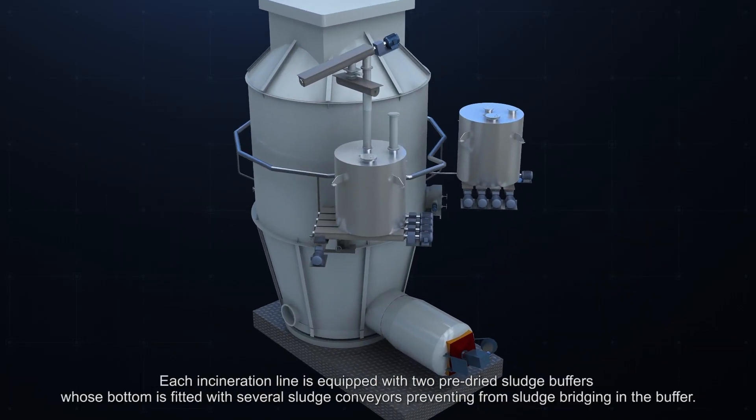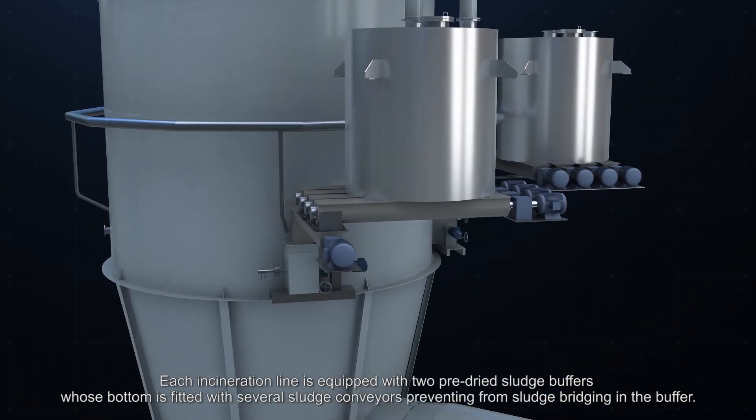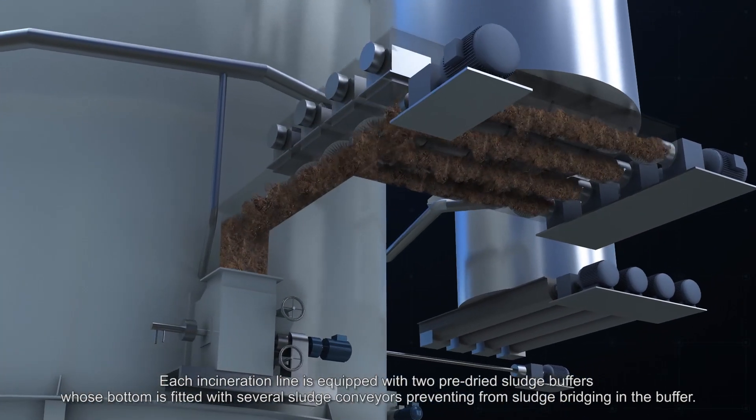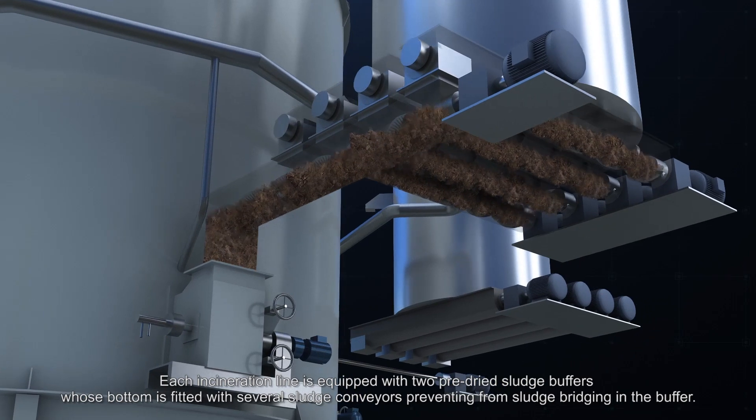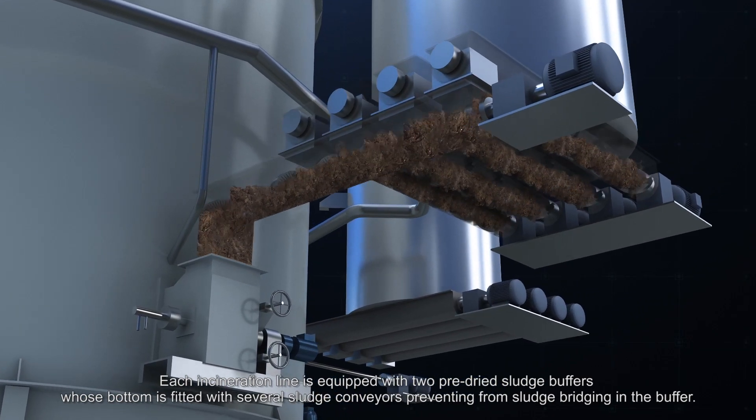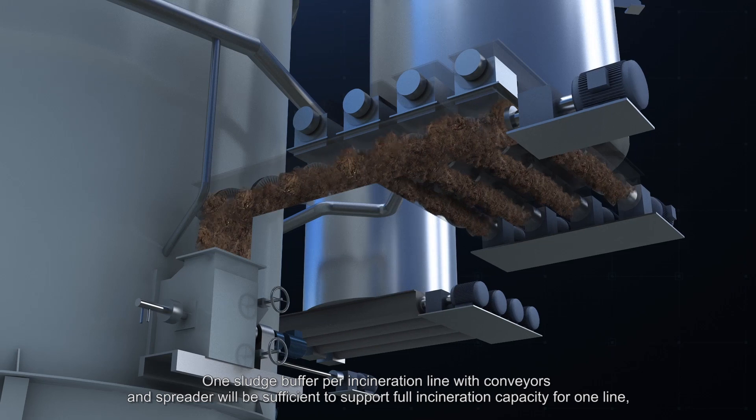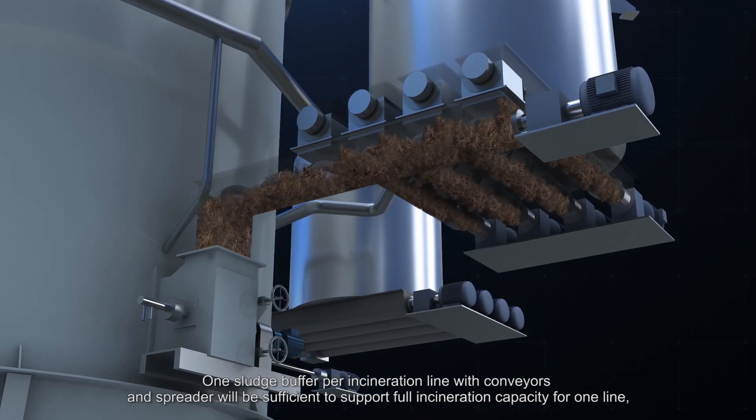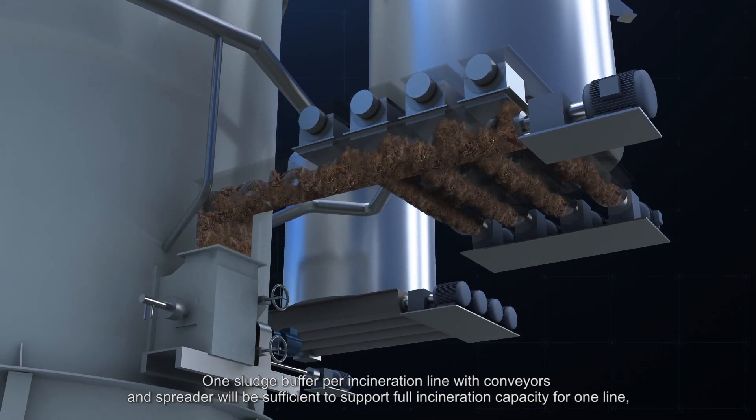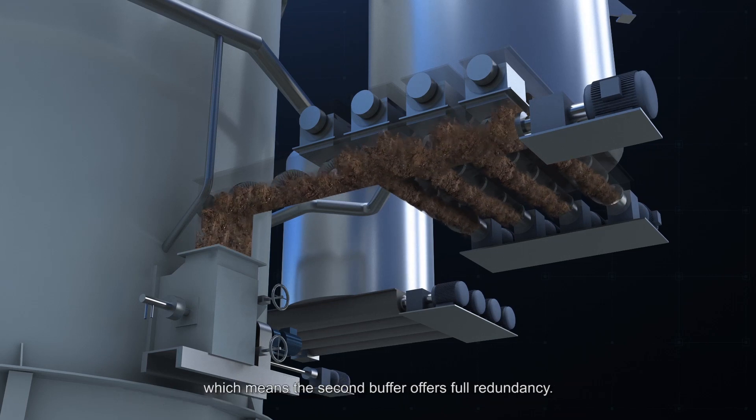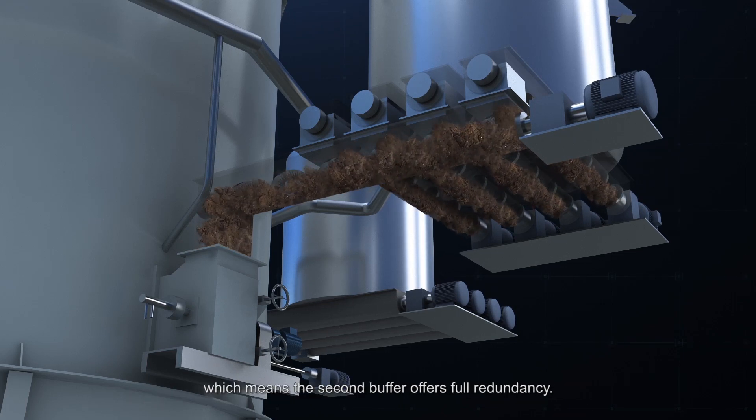Each incineration line is equipped with two pre-dried sludge buffers, whose bottom is fitted with several sludge conveyors preventing from sludge bridging in the buffer. One sludge buffer per incineration line with conveyors and spreader will be sufficient to support full incineration capacity for one line, which means the second buffer offers full redundancy.